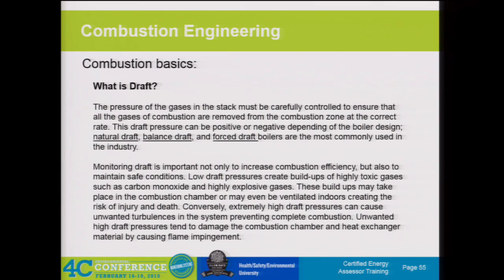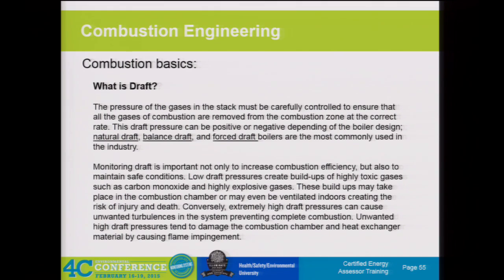The draft system is very important in the energy assessment and boiler tune-up. If we're set up with certain fans trying to balance a certain pressure in the system, any place where we have tramp air coming into the process—air coming in where it's not intended to enter—it can impact our fans' ability to supply the right pressure to the unit. We have to kind of overcompensate for that. The tighter the air system—the ductwork and the fan—the more control the operator has on tuning that air-to-fuel ratio and getting the desired results. Any inefficiencies, where we're losing air in different places, can impact how that boiler operates.